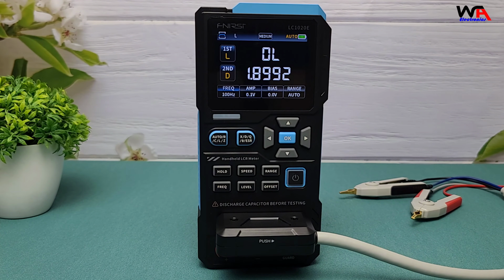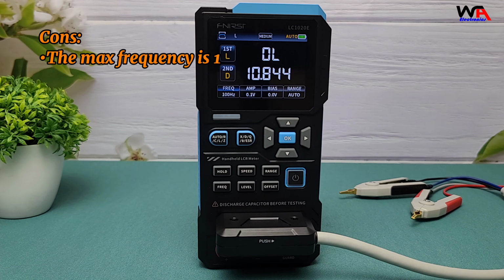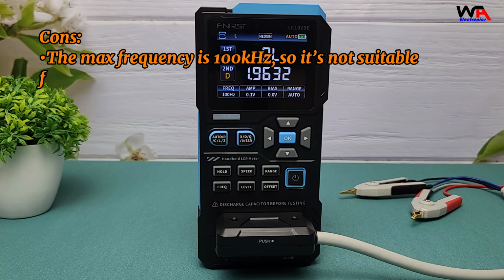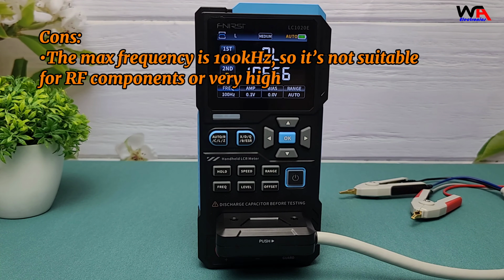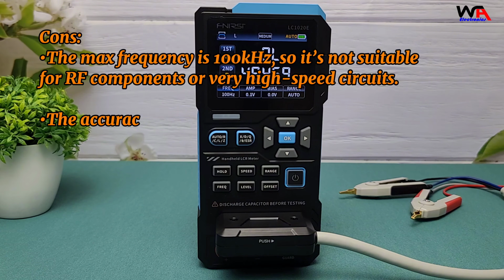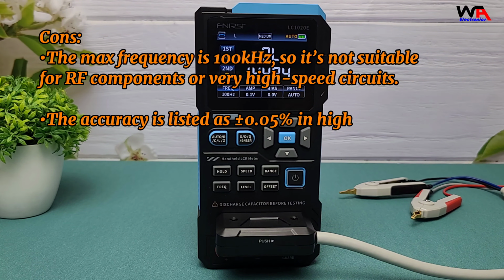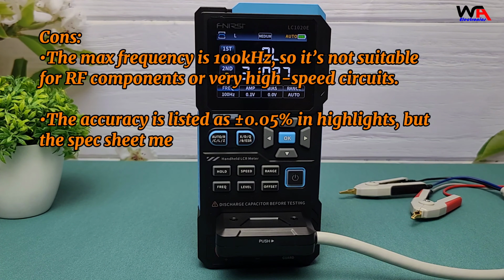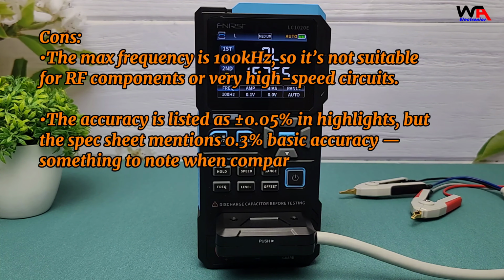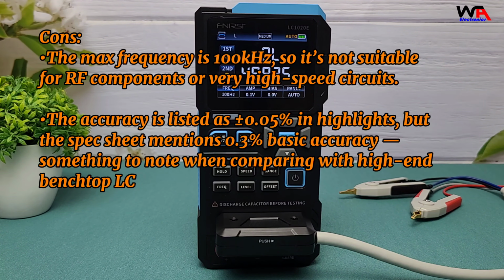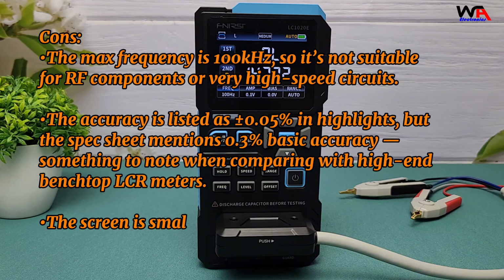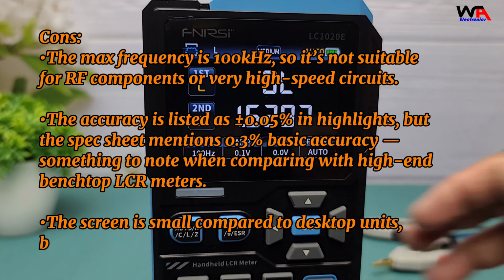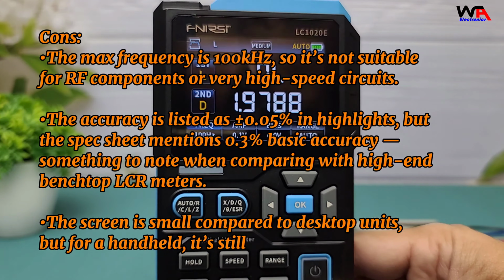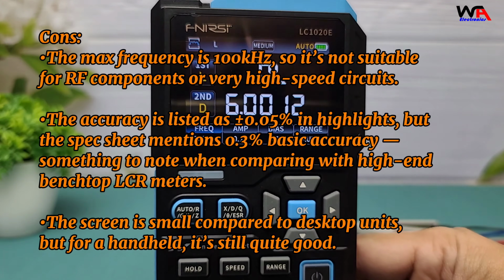Things to keep in mind: the max frequency is 100 kHz, so it's not suitable for RF components or very high-speed circuits. The accuracy is listed as plus or minus 0.05% in highlights, but the spec sheet mentions 0.3% basic accuracy—something to note when comparing with high-end benchtop LCR meters. The screen is small compared to desktop units, but for a handheld, it's still quite good.